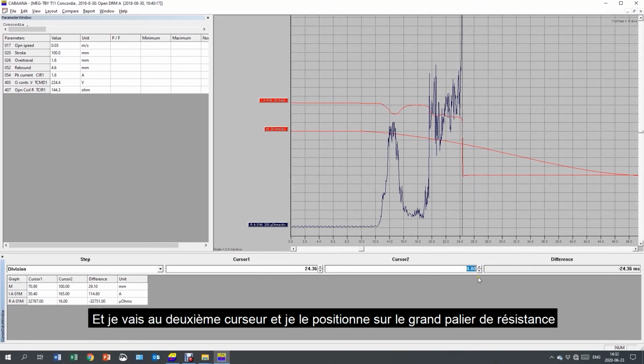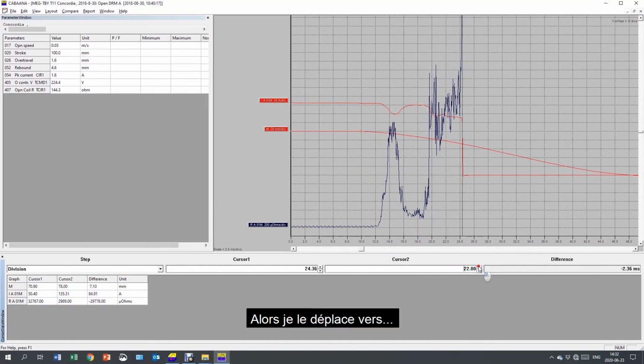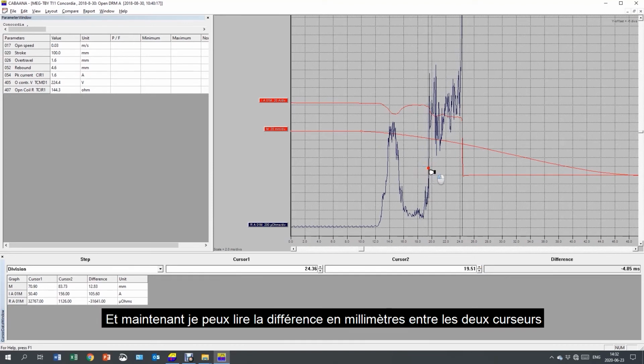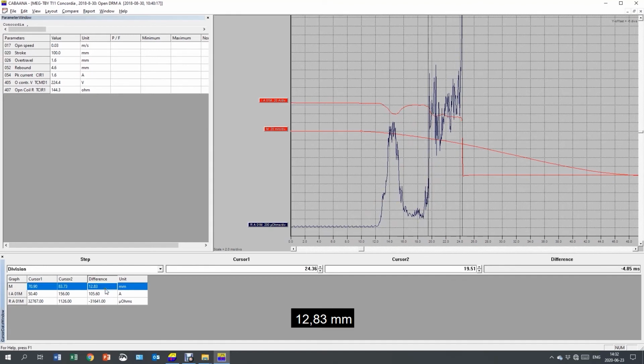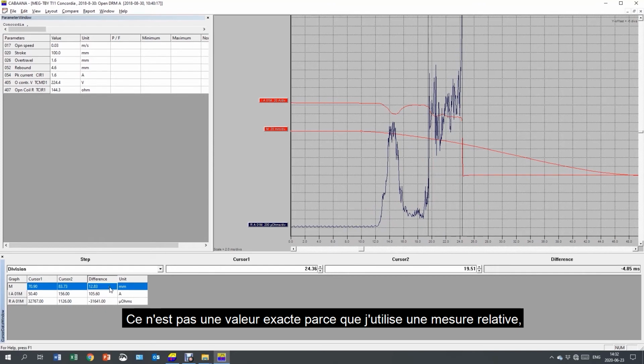And I go to the second cursor and I put it to the big resistance step. So I move it to, let's see, this slope. And now I can read out the difference in millimeters from the two cursors. 12.83 millimeter. This is not an exact value because I'm using relative, but I can have it as a reference for future comparisons. Again, I do 2 to 3 recordings more on each phase.